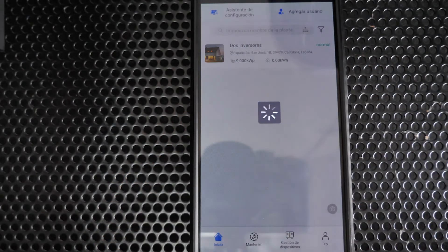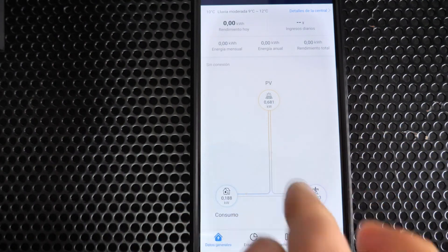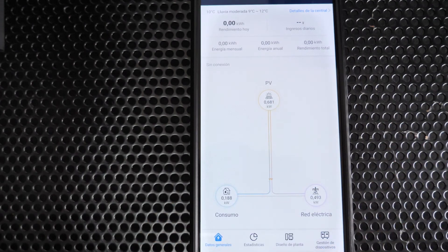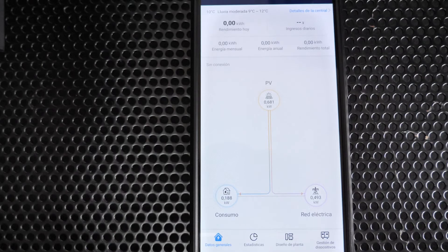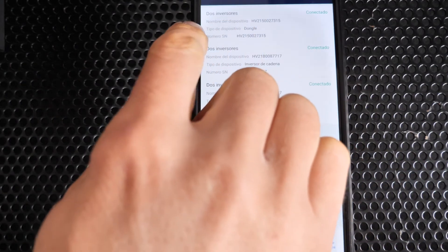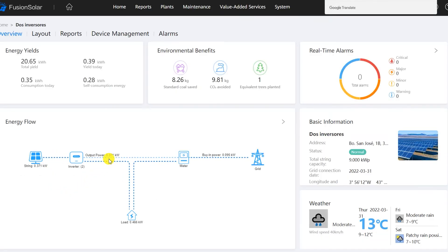After a few minutes you can start seeing the installation data. The photovoltaic plant shows two inverters with a total production of approximately 681 watts — consuming 188 watts and injecting 490 watts into the grid. In the device management section you can verify that both inverters are correctly associated: the slave inverter linked to the master, the master with the WLAN FE dongle, and the energy meter all correctly implemented in the FusionSolar platform.